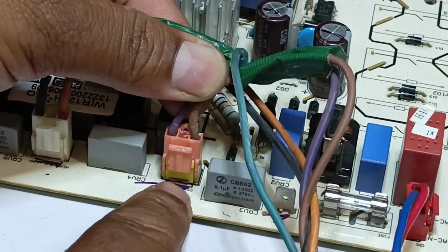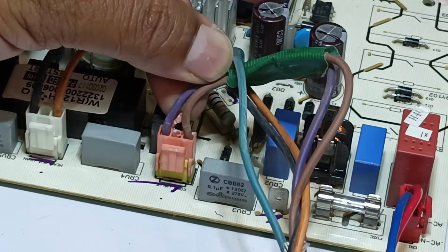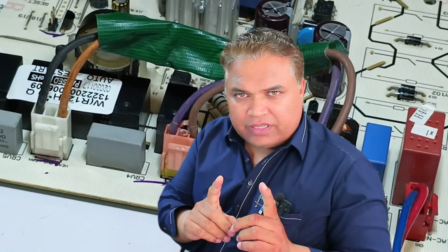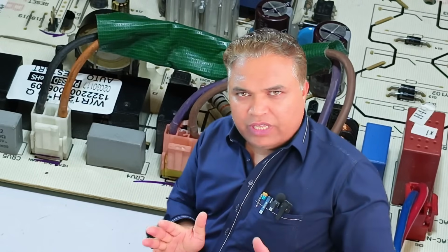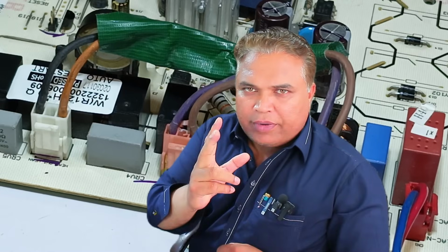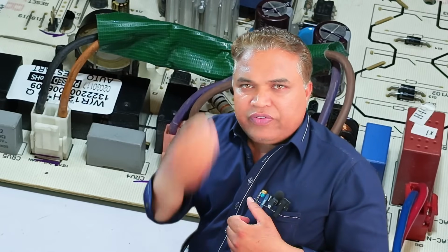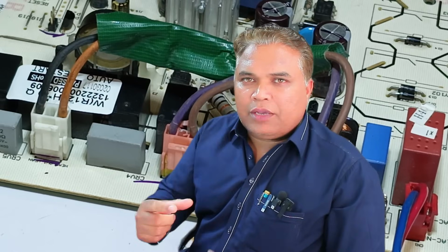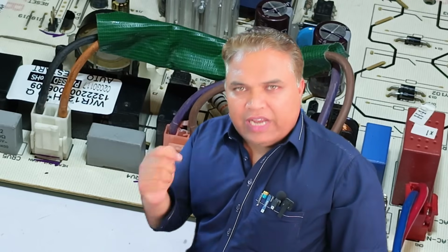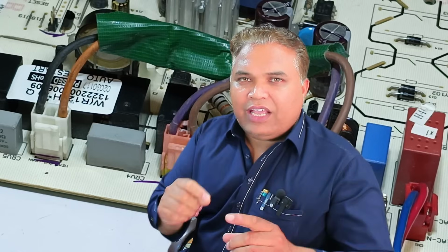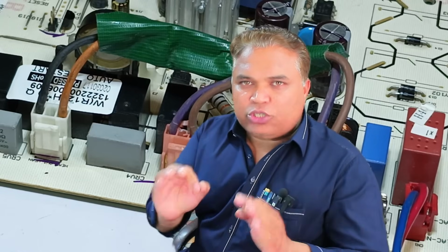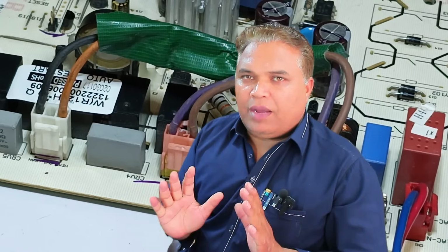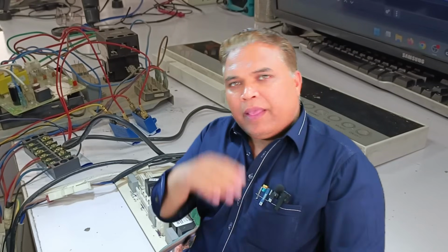Next, let's look at this connector. The brown wire here is connected to the compressor. The compressor is operated directly by the indoor unit. The outdoor unit does not have control over it. The outdoor unit only performs the two tasks I already explained earlier: sensing the presence of the three-phase signals, activating the signal relay after phase detection. This confirms whether the pressure switch is functioning properly or if there's any issue. Once these tasks are complete, the outdoor circuit's job is done. All other control functions are handled by the indoor unit.